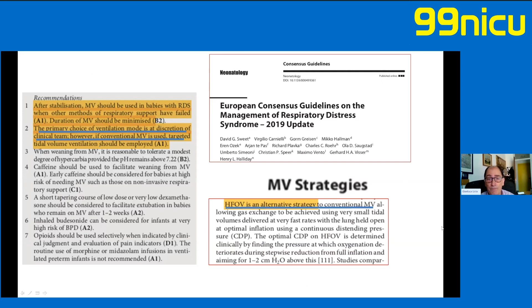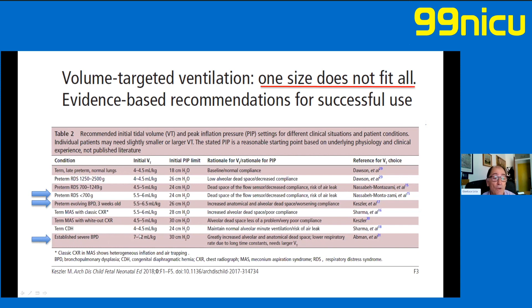The problem is that one size does not fit all, because, for example, very tiny babies suffer from the dead space of the flow sensor. So probably we have to increase the tidal volume just a little bit. If you generally use a tidal volume around 5 for a baby with a birth weight less than 1 kilo, we have to increase it just a little bit, for example to around 6, in order to guarantee a normal gas exchange. And if the baby is evolving toward BPD or an established severe BPD, because we have an enlargement of the trachea and an increase of the dead space in the lung, we have to increase the tidal volume in order to guarantee the same CO2 washout.